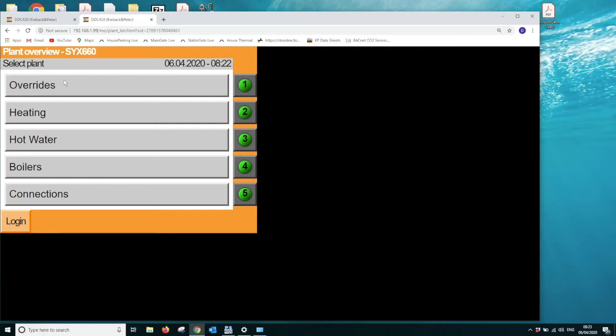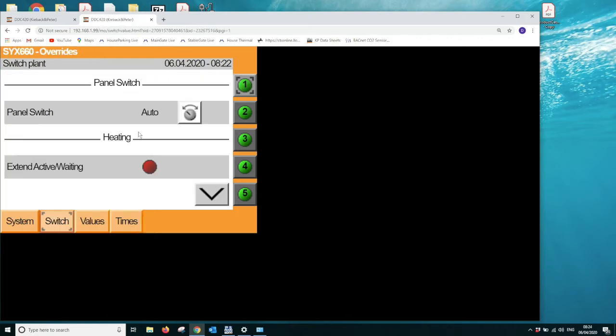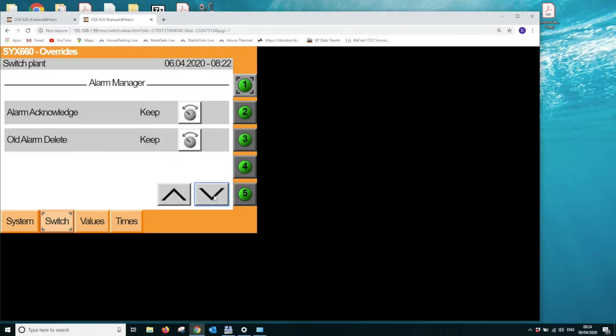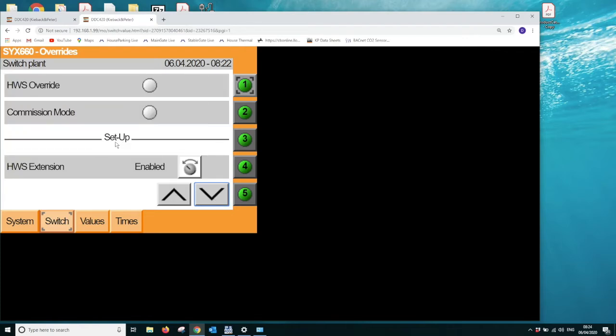So if you understand the application of the controller, the hot water signal can be connected to the auxiliary input of the SYX controller, and when there is a hot water demand, we monitor the control circuit on a volt-free contact. So when we have a demand to heat the hot water tank, we can monitor this volt-free contact, and we can then run the boiler plant to service the hot water needs. Okay, so that's what we're going to set up first of all. So we click on overrides, and we drop down to the menu where we see the option called setup.